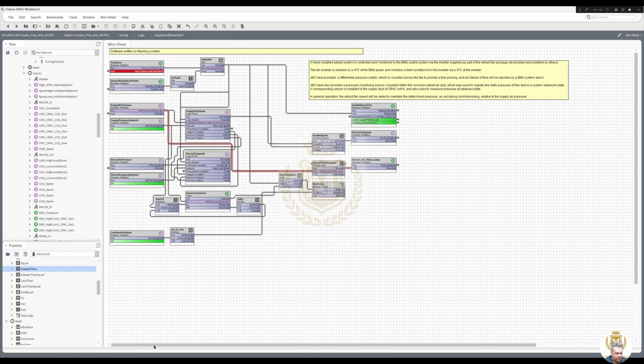Open valve. So in this particular one we need to open up the feed as well as that on all of them. So we want it to go into all of these, but I know that this one above, using a BACnet point, is only for the humidifier feed. So I need to put an OR gate at least on that one, because I can then move it. So let's just take that and that across to there. I put one OR gate. Open water valves.